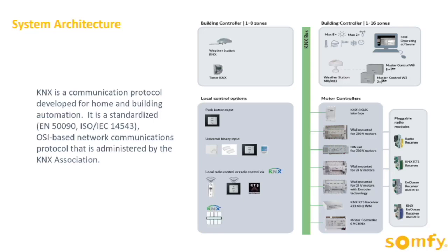We have a lot of products that work off that bus. The wall-mounted and din rail mount MoCo devices, so 4-channel 230-volt devices for standard 230-volt motors. We've got 24-volt MoCos that work with 24-volt motors. We've got the KNX RS485 interface, which you can see on top of that right-hand box. That gives us into the RS485 motors, so you go from KNX to one of those and then up to a maximum of 18 motors working off one of those devices.